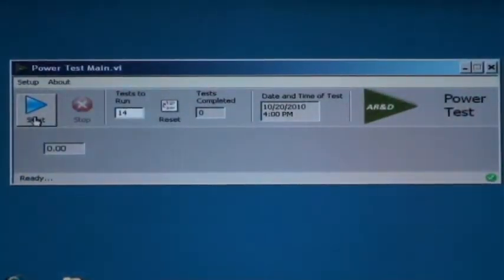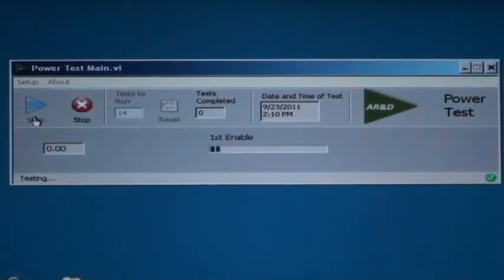Next is to engage the test. To initiate the test, the start button is depressed on the software, and then there's the first enable. The first enable loads the battery modules for 15 seconds. The next item in the sequence will be to disable the load for 10 seconds. And then finally, there's a 10-second load in which the voltage will be measured on the battery modules.